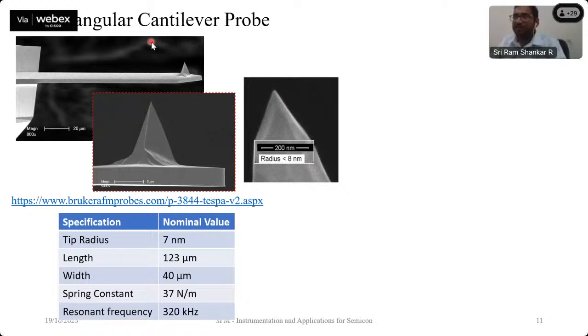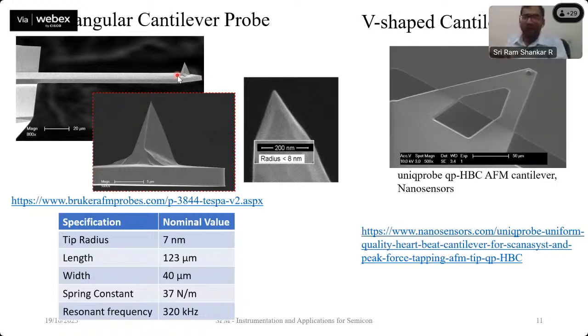So what is the probe here? The probe is the combination of both the cantilever portion that bends and the tip portion that experiences the force from the sample. We also have V-shaped triangular cantilever probes. It's still called a cantilever because it's a plank fixed at one end and free at the other end. Just that instead of the uniform rectangle, we have the triangle shaped V there in order to allow the bending.